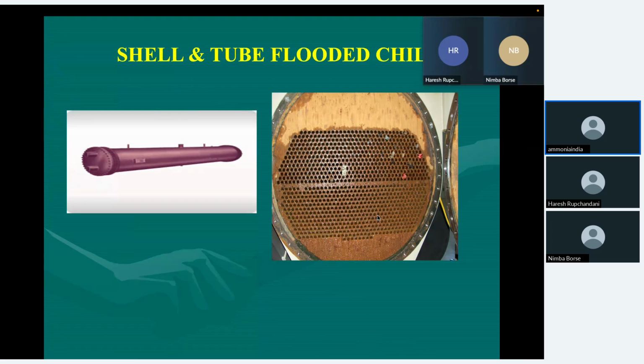Now if you see the cross section of this shell and tube flooded chiller, you will find, unlike the condenser, the tubes are not right up to the top. There is a large area left on the top of the tubes, because when ammonia boils vigorously, there are a lot of possibilities of liquid coming to the compressor. So in order to avoid liquid coming to the compressor, a gap is left in the tube bundle, because the ammonia boiling heat transfer coefficient is very high, and there is a possibility of droplets entering the suction line. We'll discuss subsequently the advantage of a surge drum, but while manufacturing the chiller also, a precaution is taken. The tubes are not filled right up to the top.